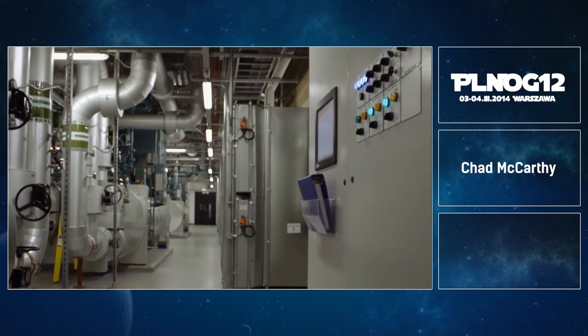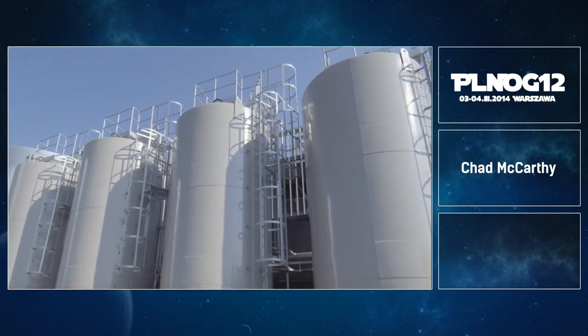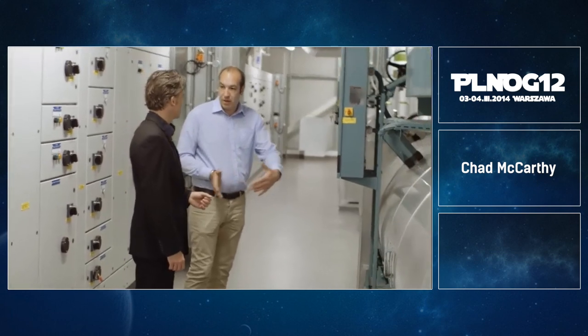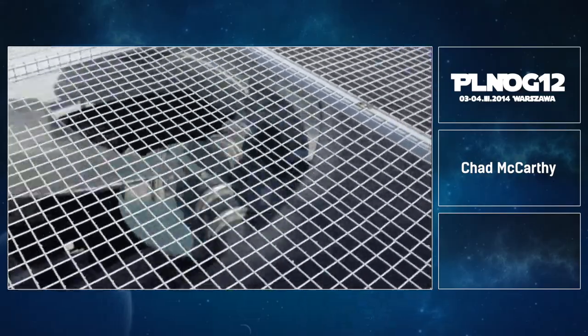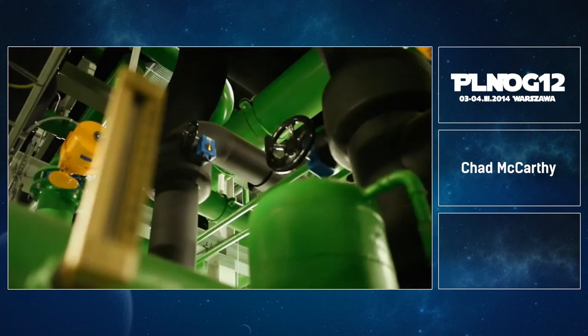We're in one of the main chilled water plant rooms of our largest London data center. It's called Powergate. This room's interesting because this is where we exchange the heat from the IT equipment in the data center and move it to atmosphere. And in terms of environmental friendliness and energy efficiency, the important thing is to take cognizance of the ambient conditions. We exchange the heat from the data center into a water circuit, which then goes to high level and is emitted to atmosphere, which means we don't run mechanical plant, we have a lower electrical power requirement, and overall we reduce our CO2 footprint for the data center. We're certainly at the front of the market in terms of cooling efficiency and efficiency of cooling systems.